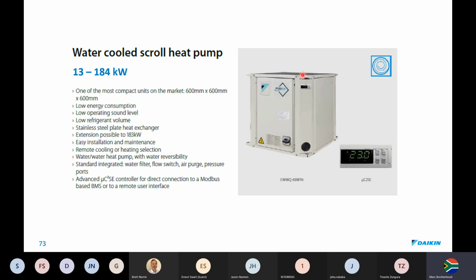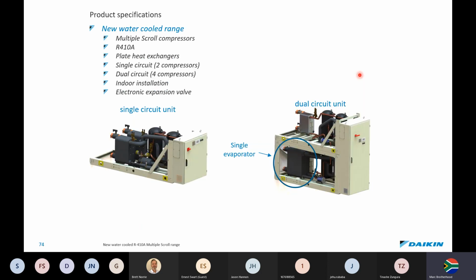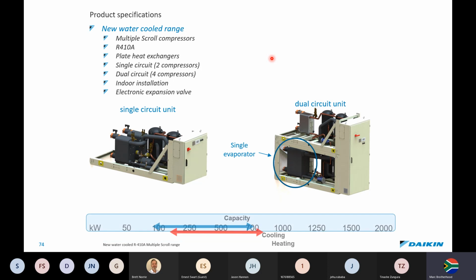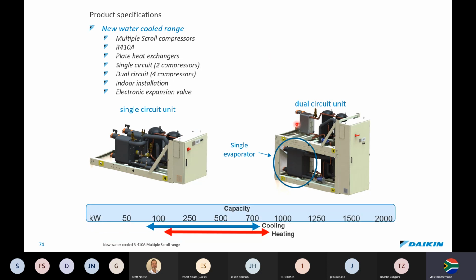So these are little Hydrocube units with scroll compressors and water-cooled chillers with remote condensers, ideal for little indoor applications. We have multiple scroll compressors which you can stack on top of each other. So this would be your single unit, and then we have a dual circuit to parallel the capacity. Also indoor installation, all our units come with electronic expansion valves, and here you can see the brazed plate heat exchangers. This is all designed to be very compact and fit in small areas. And we can go up to close on a megawatt in heating operation and just over 700 kilowatts in cooling.